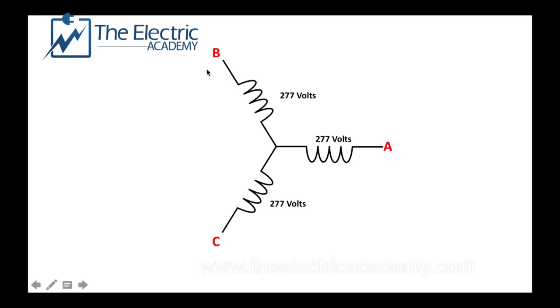Now what happens here is I've got three phases - A phase, B phase, and C phase. The way that this is connected, you notice that A phase has got 277 volts on it, B phase has 277 volts on it, and C phase has 277 volts on it. But when you throw your meter, if you go from A to neutral you're going to read 277, but if you go A to B you're going to read 480.